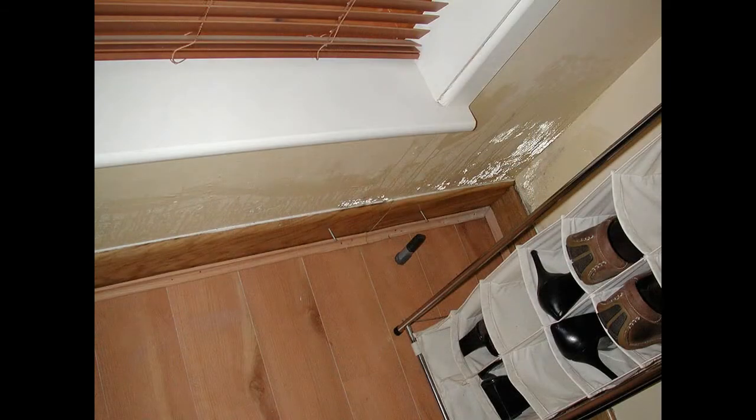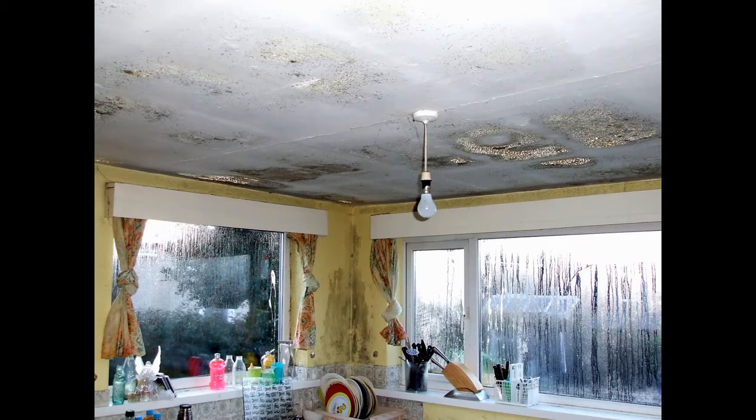In this case it was severe. Here it is on paper, the lower part of a wall. That area up to about 1 metre was below the dew point, and it occurred in all the flats. More visual assessment. It's a bit of a serious one, this one, but there's plenty of water around to see, caused by surface condensation.